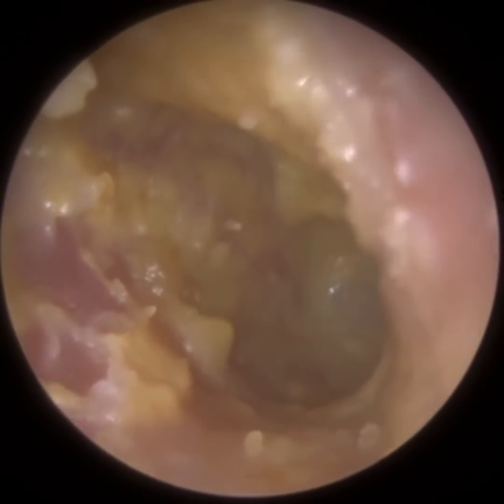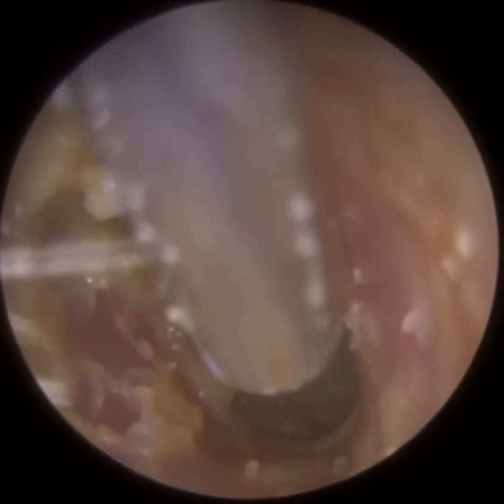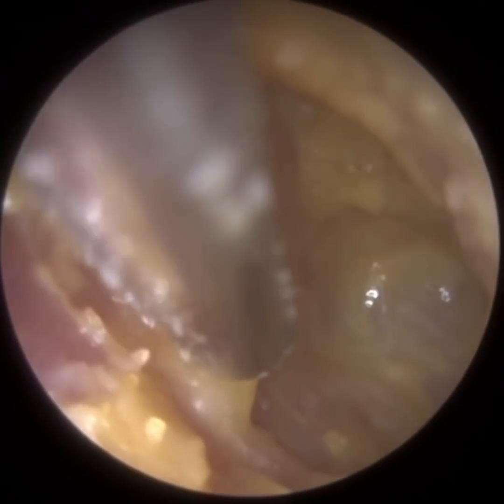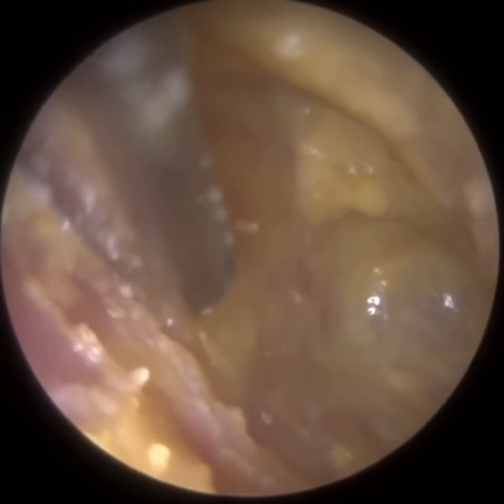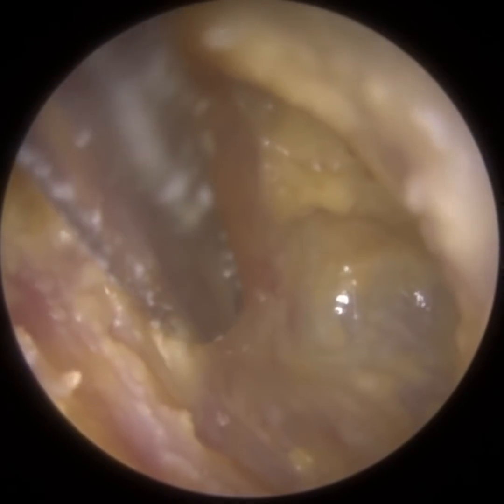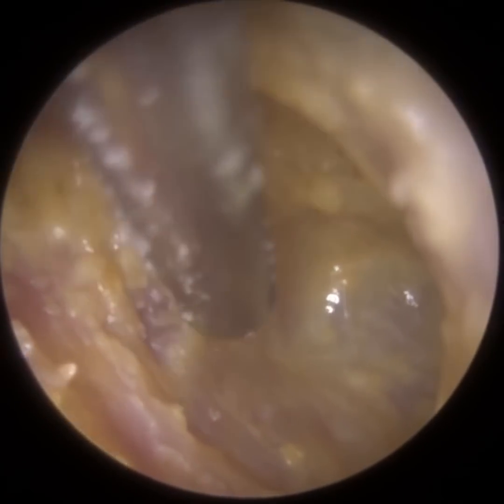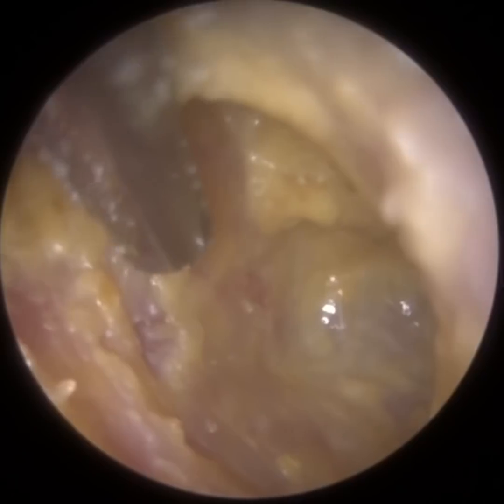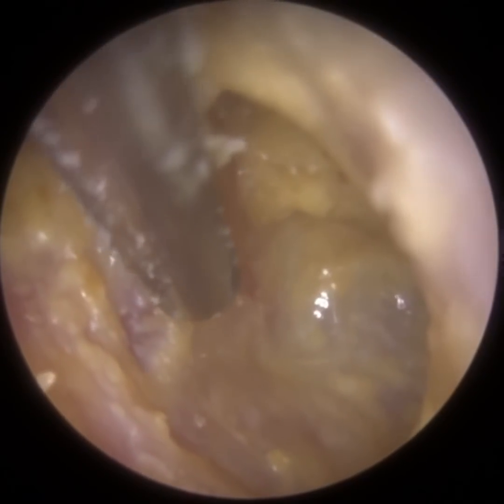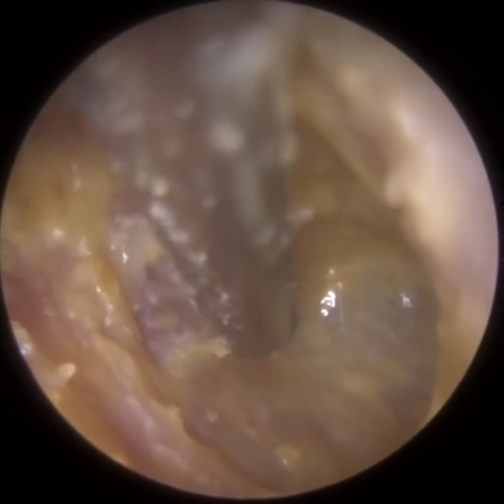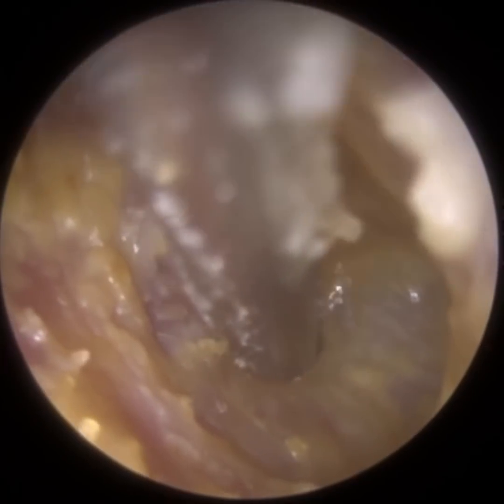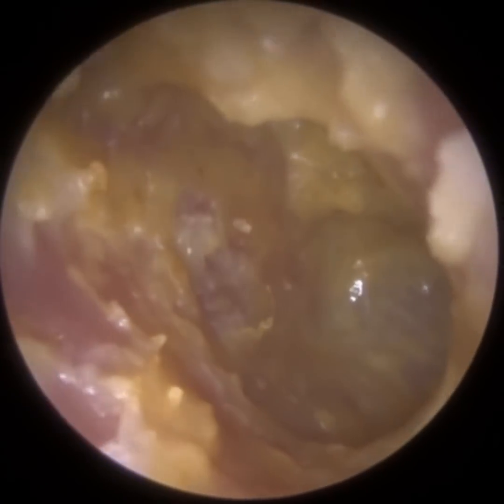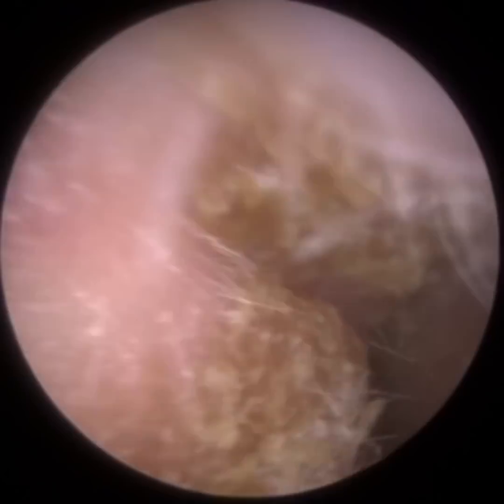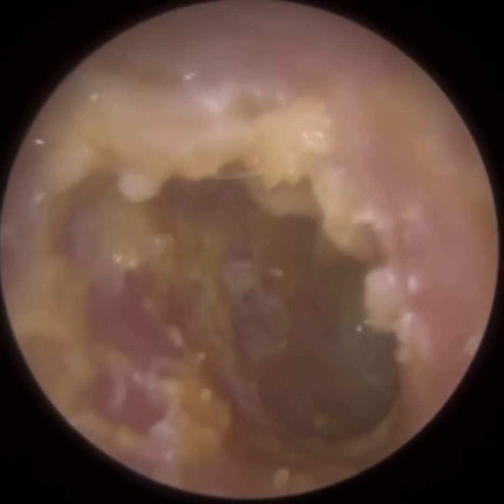And because this surrounds the lenses, the heat from the light dissipates evenly around the endoscope, which then, if you leave the endoscope in the ear for 30 seconds or so, it will heat up the lens sufficiently to the surrounding temperature, which will then cause that misting to disappear and evaporate. Alternatively, as soon as you put the suction probe in, it helps to evaporate that misting.